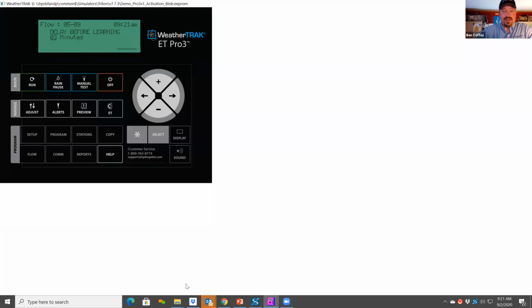Jonathan, do you have any other examples of when you change that? Yeah, so if you do happen to get high flow alerts, and you go back and check the station and notice that everything seems okay, it could be that there's just more fill time needed that you're not seeing. So if you have one of those ghost high alerts that you can't figure out, that might be one of the things to look at. Absolutely. All right, there we go.